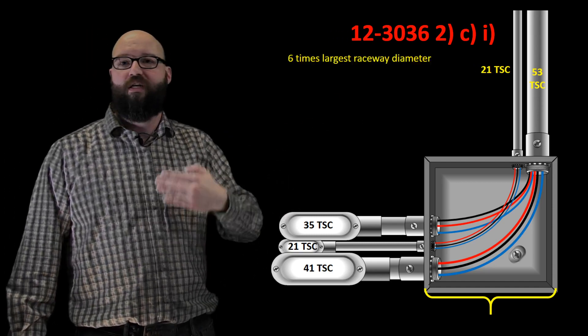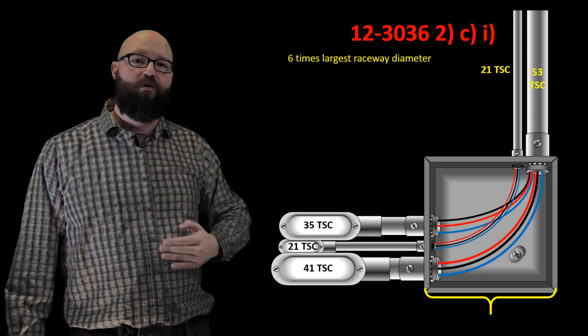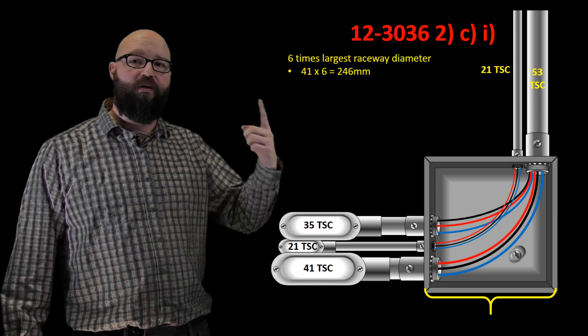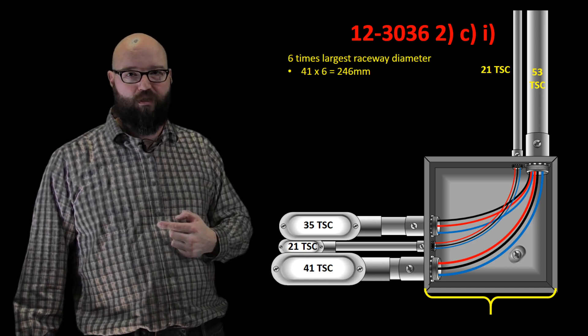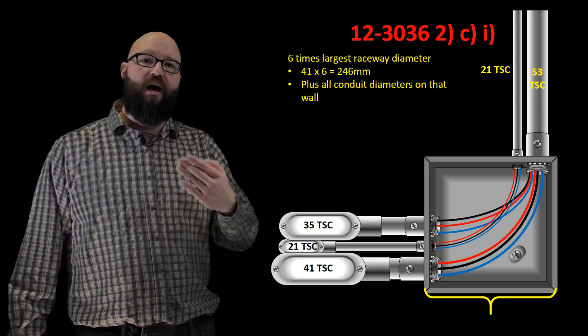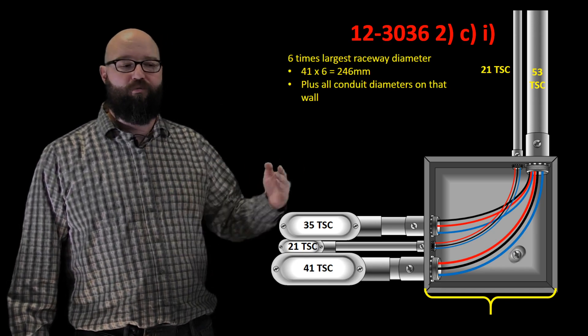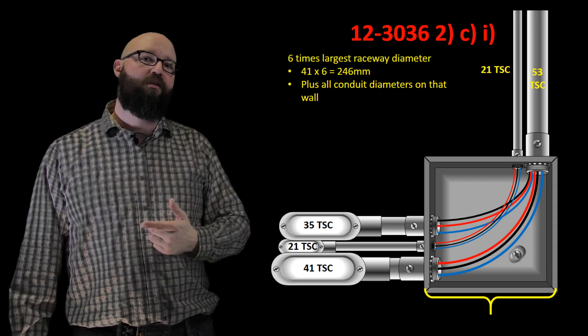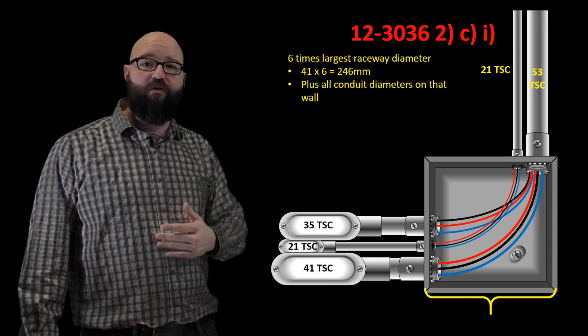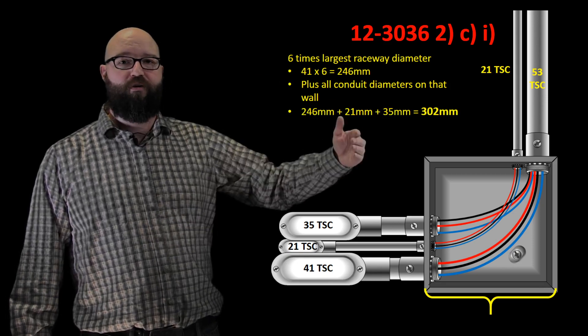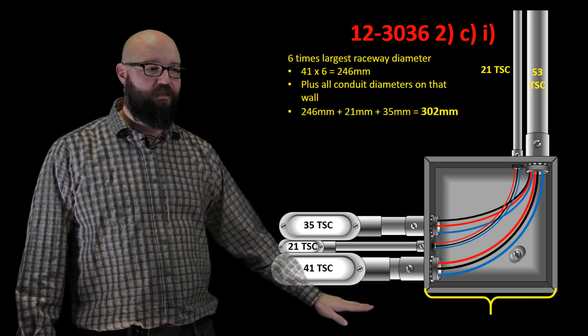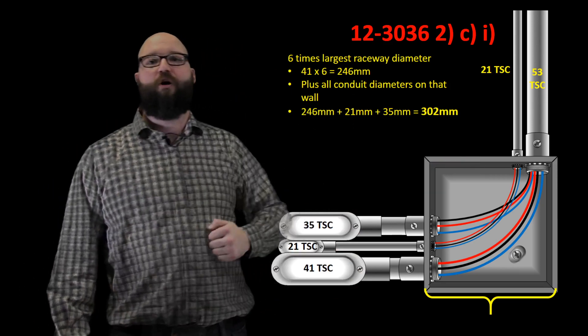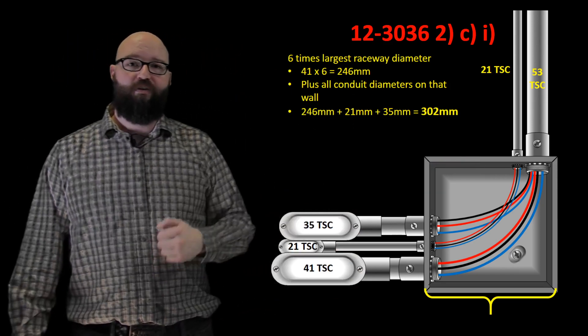Which in this case we have our 41 times six gives us 246 millimeters. Then what we're gonna do is add to that the rest of the diameters from our other raceways on this wall. We have our 21 and our 35 trade size on there as well. If we add those on to the 246, we end up with a total of 302 millimeters. That's the minimum distance to observe that we have the proper distance to the opposite wall there. So that's one dimension.